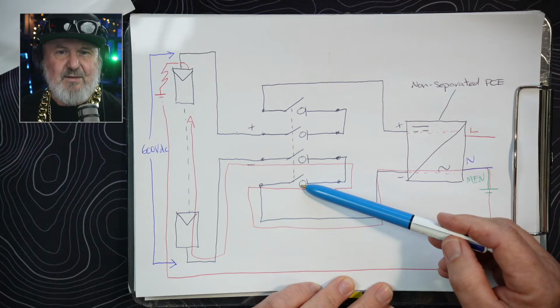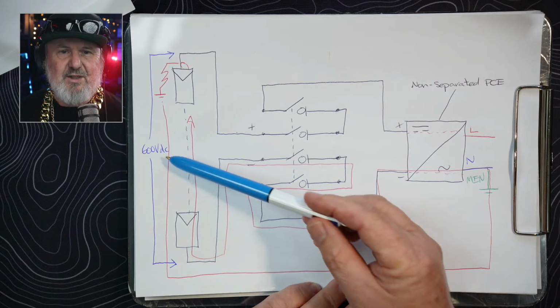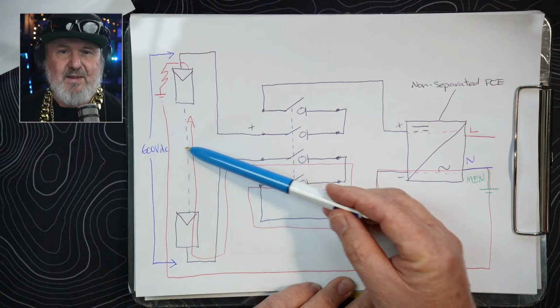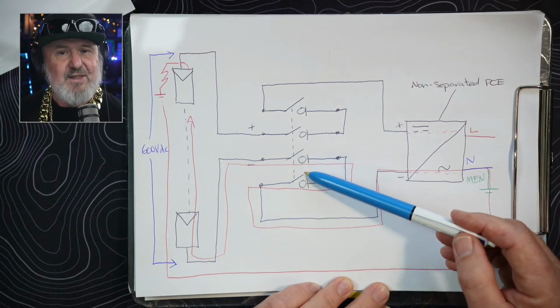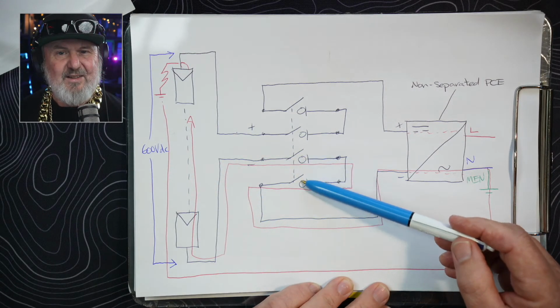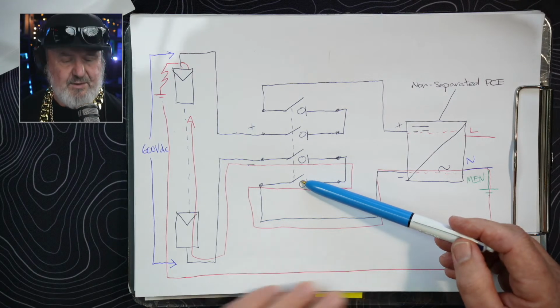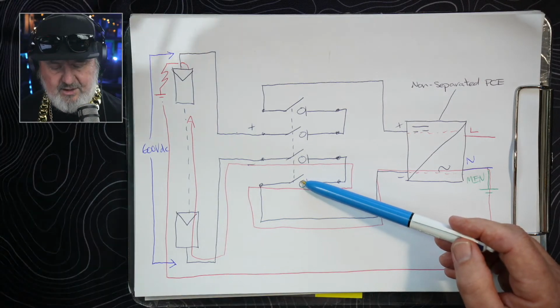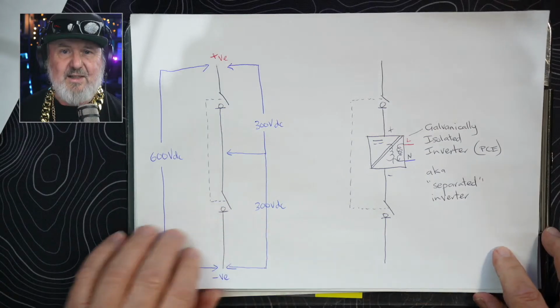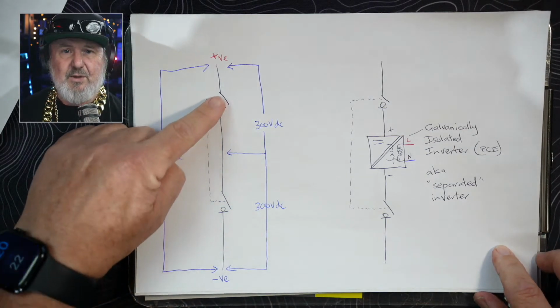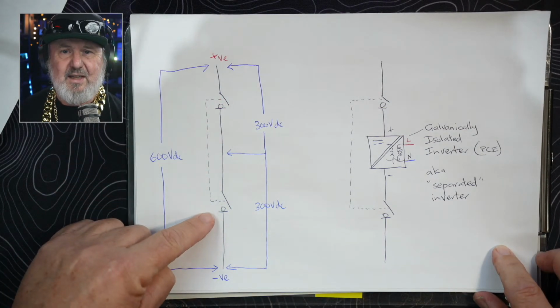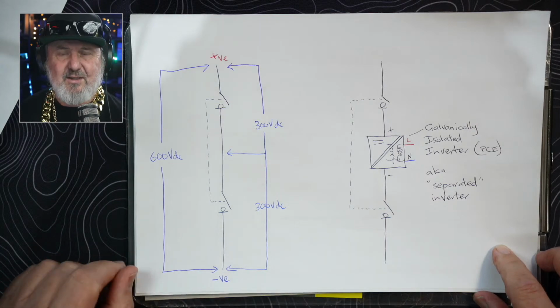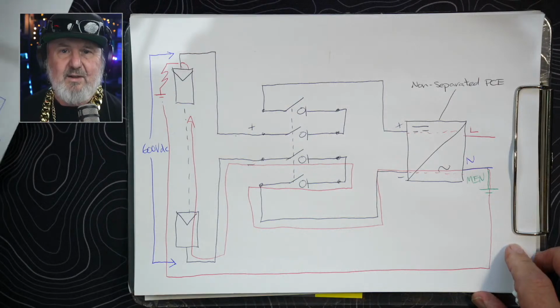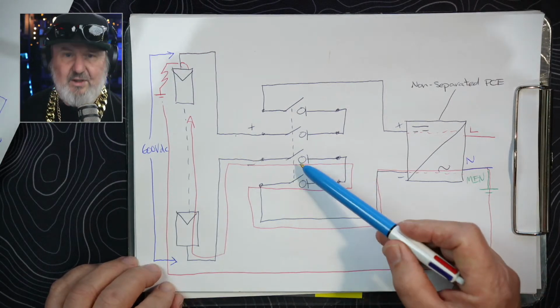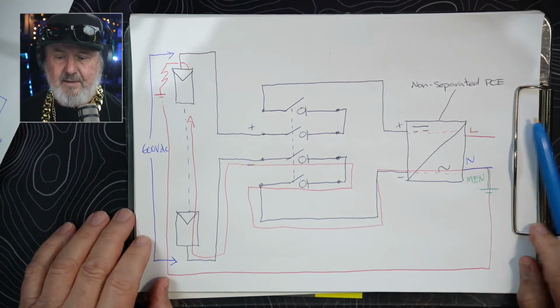So we've now effectively moved this 600 volt open circuit problem across just half of the DC isolator. So those 2 poles have to break 600 volts. Not like in our earlier example with a galvanically isolated inverter, where we're separating it to the positive side and the negative side, 300 volts each. Now with a non-galvanically isolated inverter, we've got to switch it on just one side.